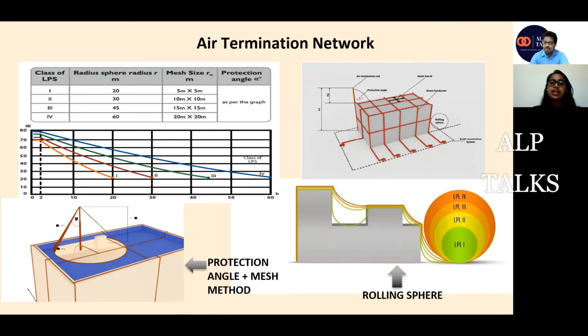So if I am designing my building at level 4, I'll make a complete mesh of 20 by 20 meters over the roof, and I will connect it with the down conductors coming from the roof to the ground. So it is a complete mesh which will be installed over the roof. And how is the rolling sphere method different?